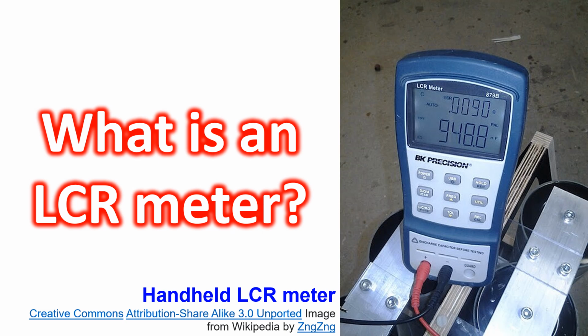LCR meter is an instrument used to measure inductance L, capacitance C, and resistance R, as the name indicates. They can measure the impedance to a sinusoidal waveform of definite frequency and convert the measured value to capacitance or inductance. Higher-end machines can measure true inductance or capacitance, equivalent series resistance of capacitors, and Q factor of inductors.